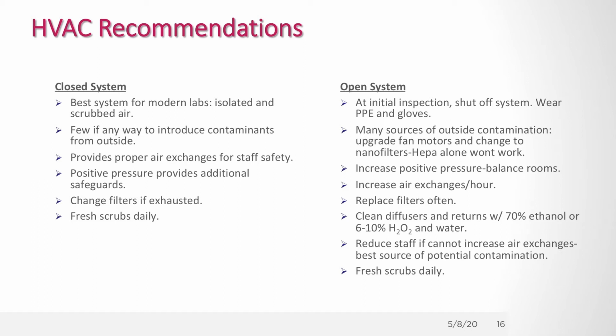Realize that if you have HEPA filtration in these scenarios, it doesn't help. You need to install nanofiltration, meaning you filter down to the nanofilter level. If you do that, though, it's going to require quite an upgrade in fan motor to deal with the added resistance you'll get.